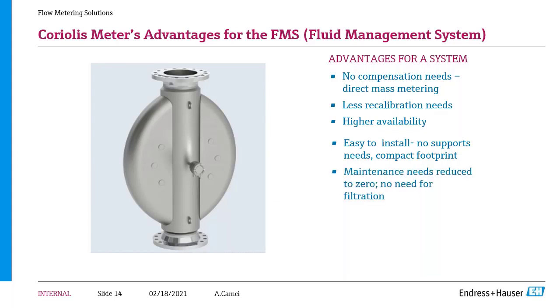As I said, it doesn't have mechanical moving parts inside, therefore the maintenance needs reduce to zero. It is just a pipeline if you consider it like that, and there is no need to make filtration so that you don't damage gaskets or blades or anything else for the measurement accuracy. It gives you a kind of process transparency because it is direct density measurement. It is directly measuring the density.